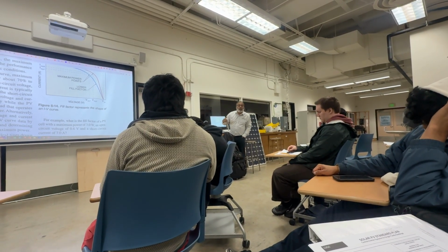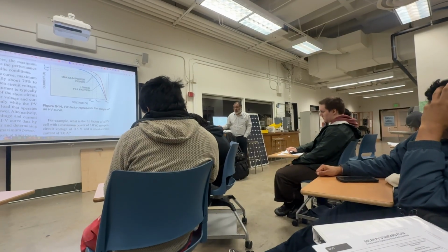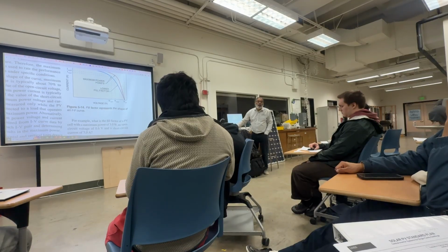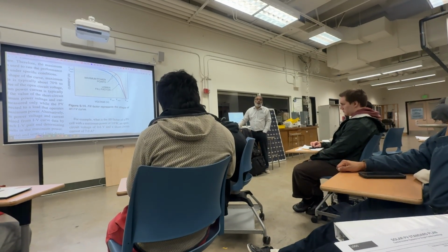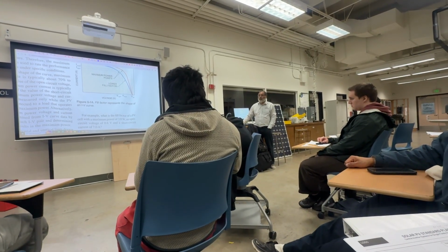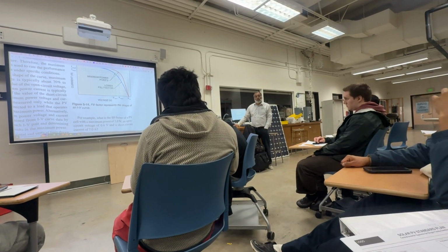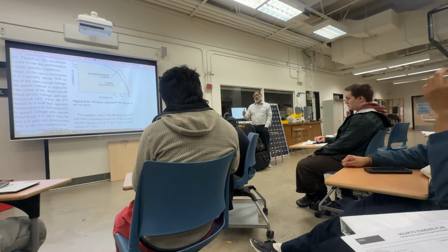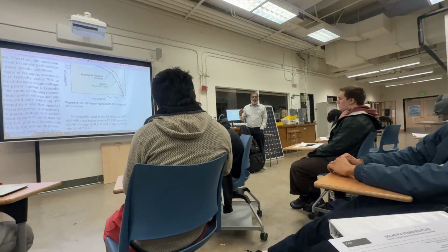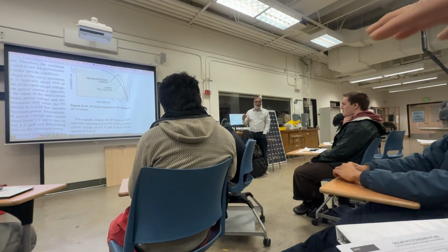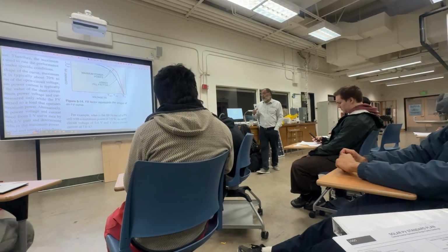So you want to make sure that you size the conductors the proper size. Except for some special equipment, there's no voltage drop in California that's enforceable. Oh, I see. 210 is unenforceable. It's just good practice. Because we want to be good electricians out there, right? So you're saying I have tables to calculate the correct size, but in reality, whether I follow it or not, there's nobody actually forcing me to follow it. But then I'll catch on this curve if I don't follow those rules.